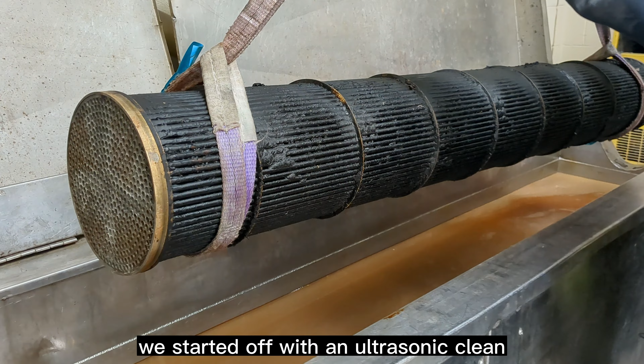First of all, we started off with an ultrasonic clean, putting them in a very hot soak, because the material we remove from this is carbonized coolant. If it's not too cooked on, it should just melt away in the ultrasonics. With a little jet washing in between, we should slowly remove all the particulate from in between the heat exchanger. But that's not actually how it ended up.